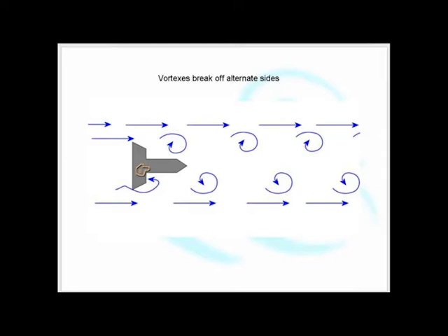It flops down. There's a cut-off point. Basically, you need to get to a certain velocity before it starts to flap. It's the same with a vortex flow meter. There's a very, very sharp cut-off point, and below that velocity, it doesn't measure anything. So it's a good, accurate flow meter, but if the velocity is too low, it measures nothing, and then it suddenly starts reading when you get to the correct velocity for the flag to start flapping.